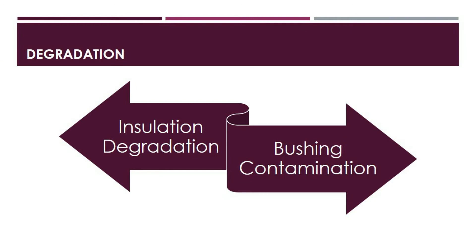Let us first start by understanding what are the modes of degradation for distribution transformers. Distribution transformers are degraded by two key factors: the first one being the degradation of the transformer's solid insulation and insulation oil, and the second one being the contamination of the bushing and its exterior surfaces.